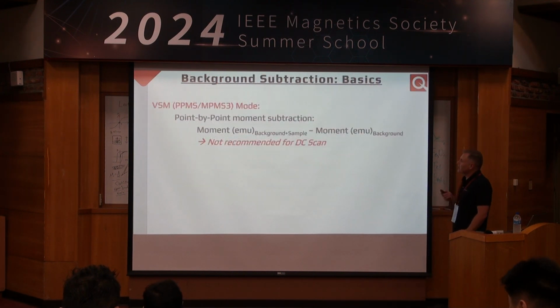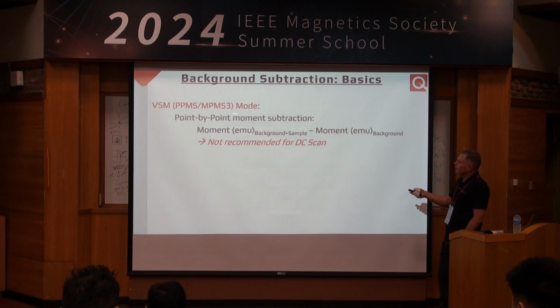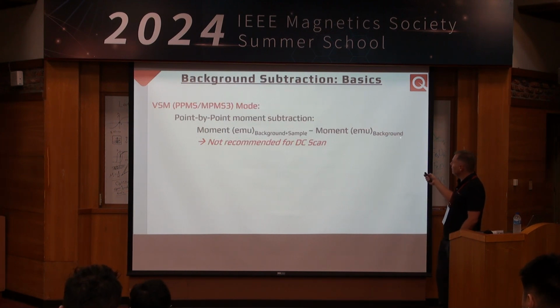So, background subtraction, the basics. For VSM on the MPMS3, if you're doing the SQUID VSM mode, a point-by-point subtraction is pretty much all you need. You want to have the moment of your background plus the sample, and you just subtract off the moment of your background. Ideally, you want to have whatever sample holder you have. The only difference between these two measurements is the sample. And usually you can get away with this.